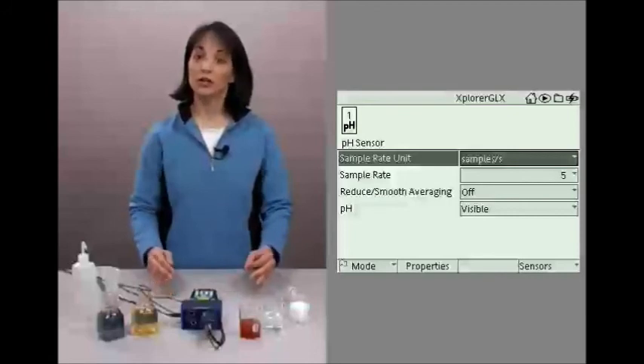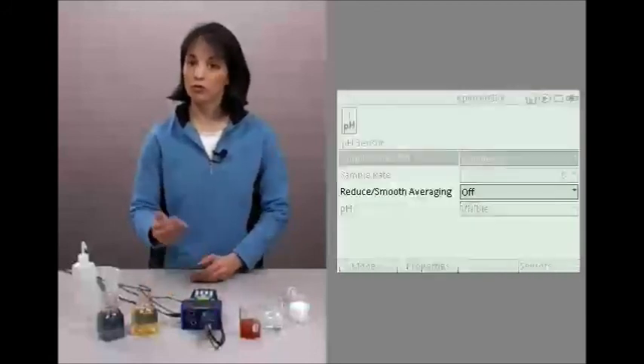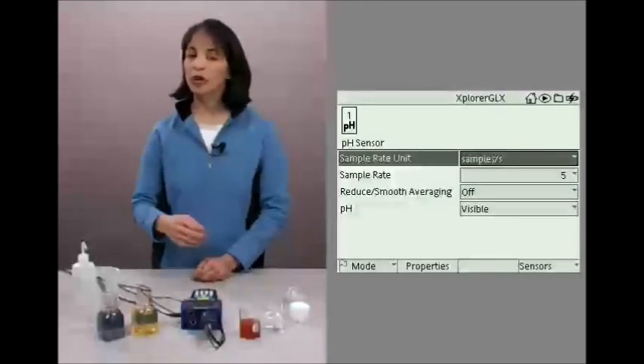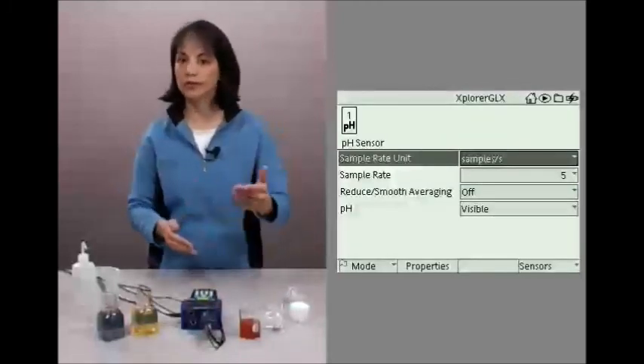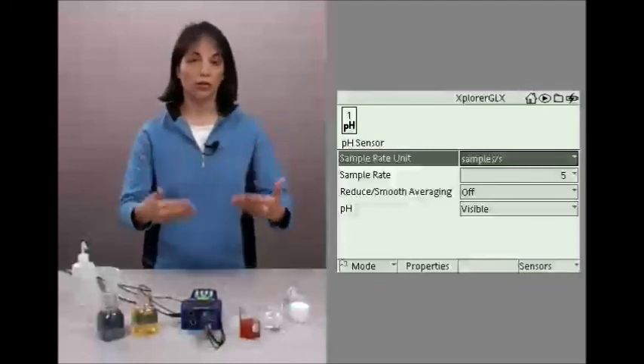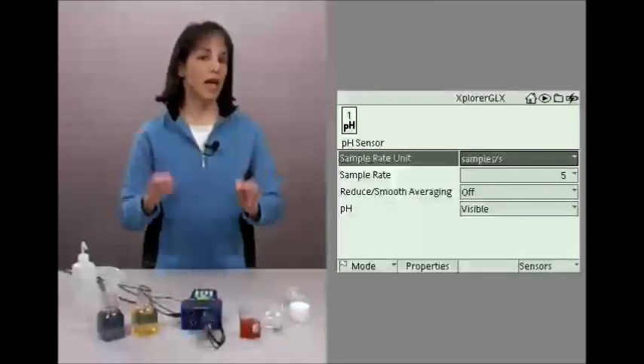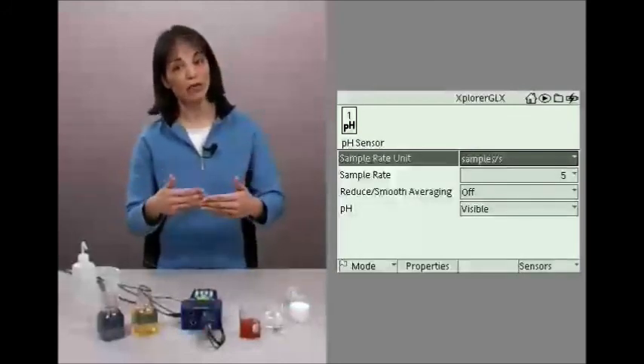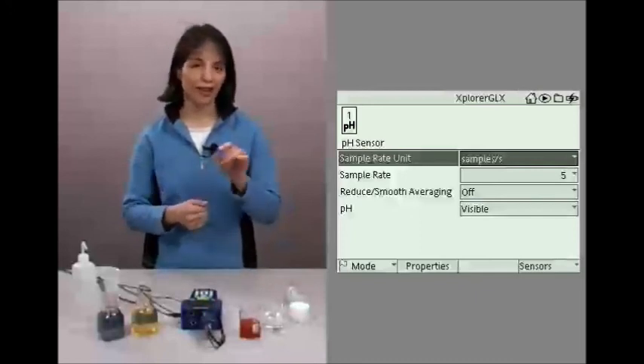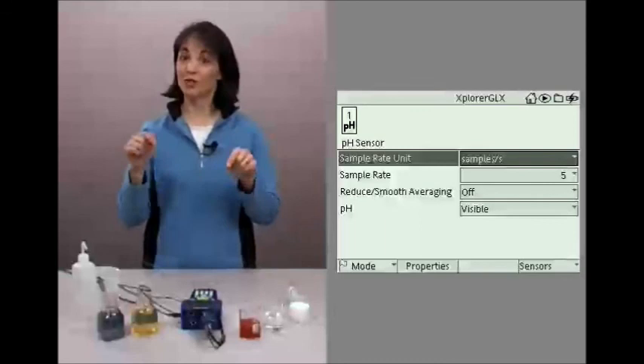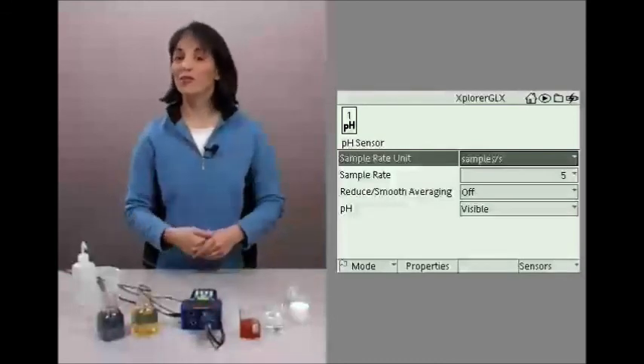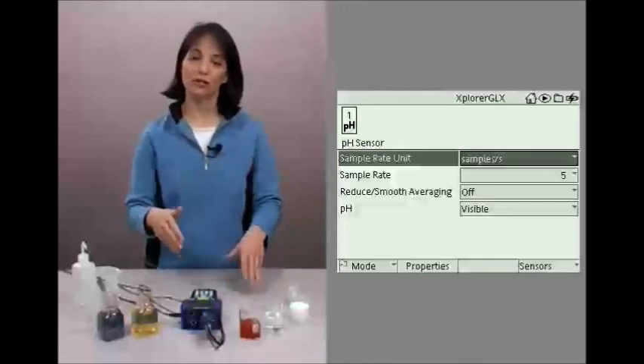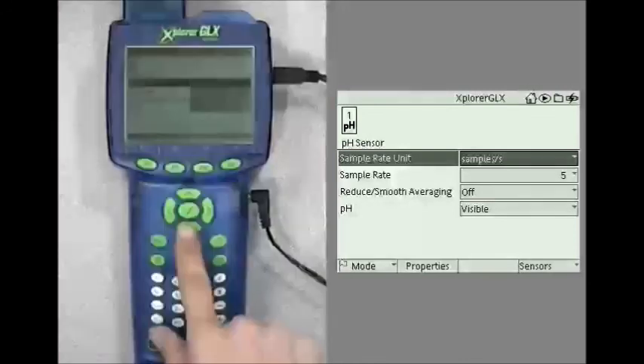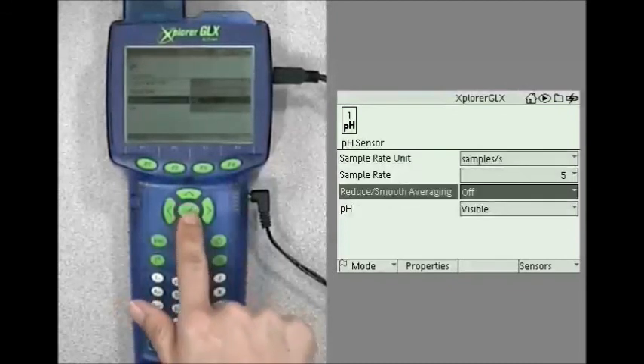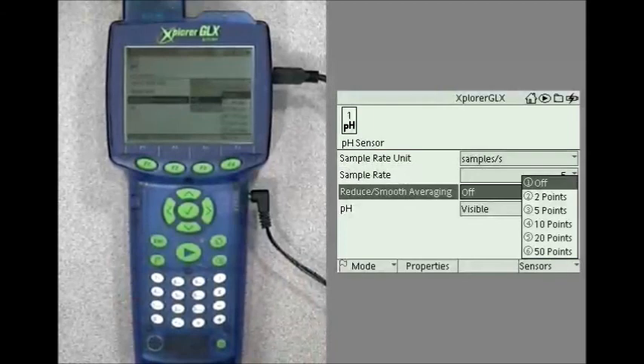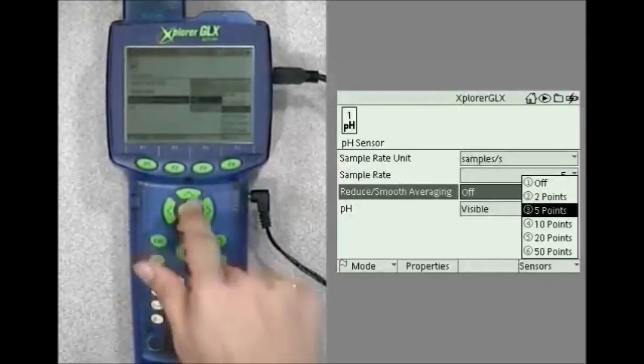And the last thing to do here is to explain to you what the reduce/smooth averaging field is. Now, if we were good experimenters, we would not record just one data point for each sample. We would determine several data points, average them, and report that average as the pH of our sample. That's what that field is for. So we can tell the Explorer GLX to do that for us. And the only thing we have to do is tell it how many points we want it to use to calculate the average. So let's scroll down to that field with the arrow key, push the check mark to open up our options there, and let's select, say, 5 points, and check mark.